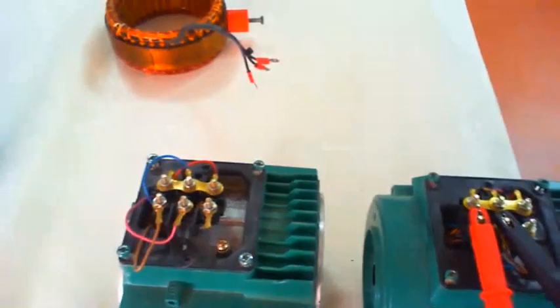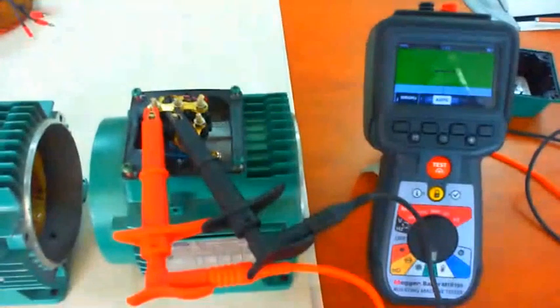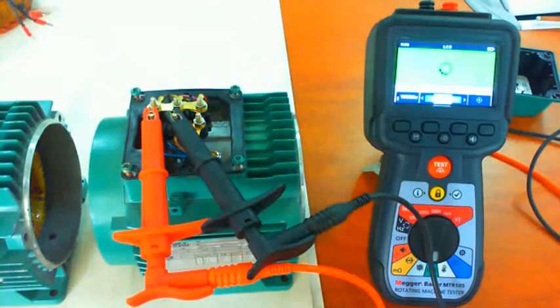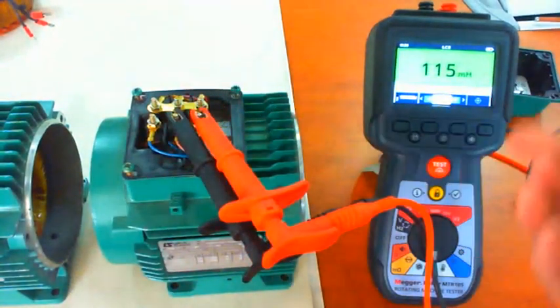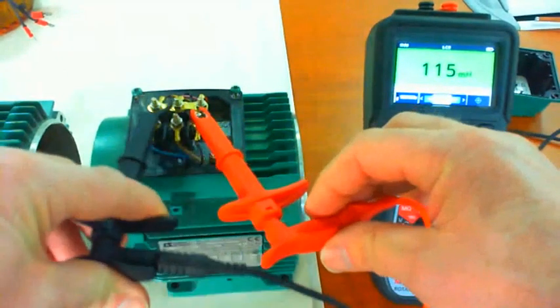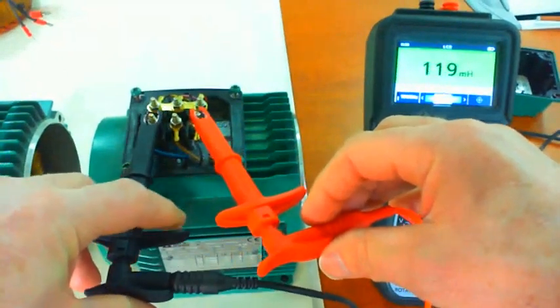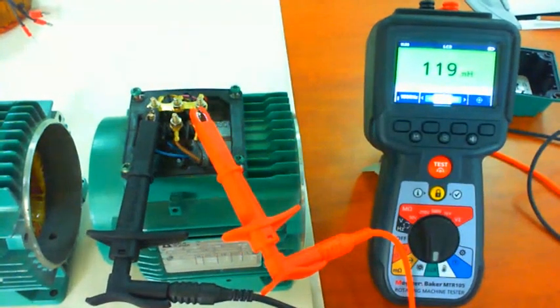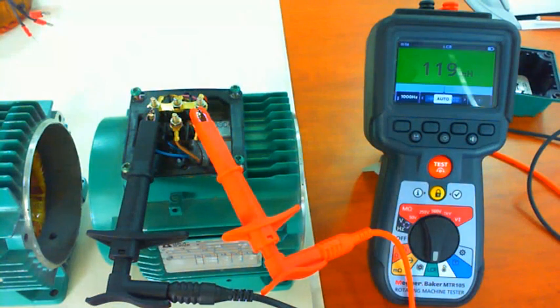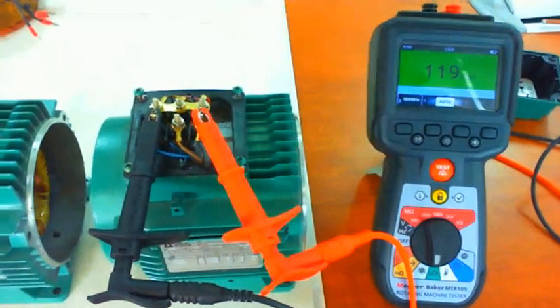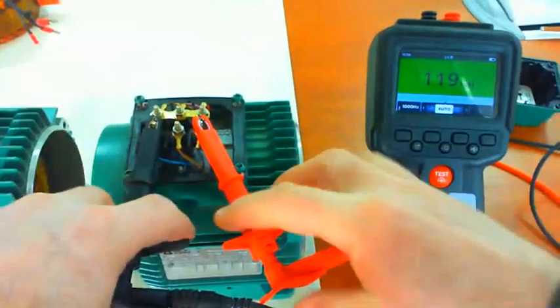So first of all, we're going to measure the inductance of the good stator, which is this one. So inductance, we've got 113 millihenries, 115 V to W, and 119 W to U. So slightly unbalanced, but again, that's because it's a two-pole winding. So now I'm going to test my other stator.